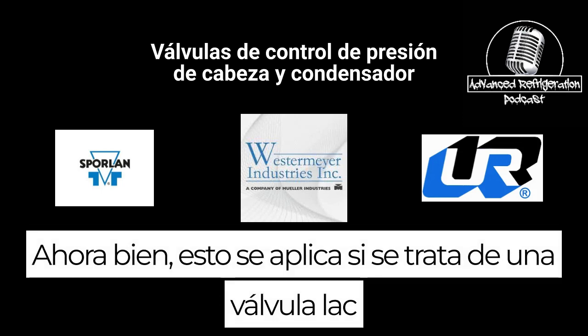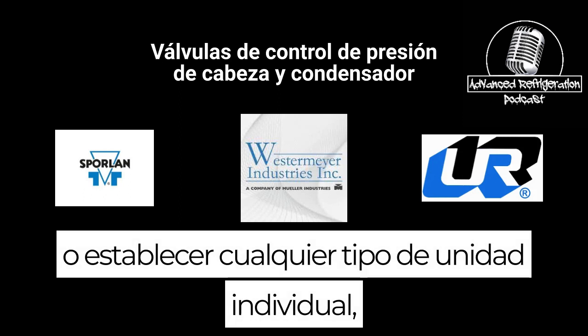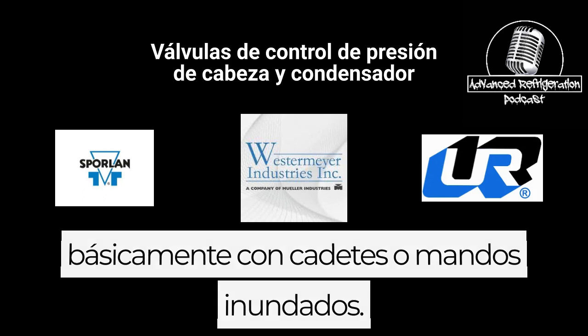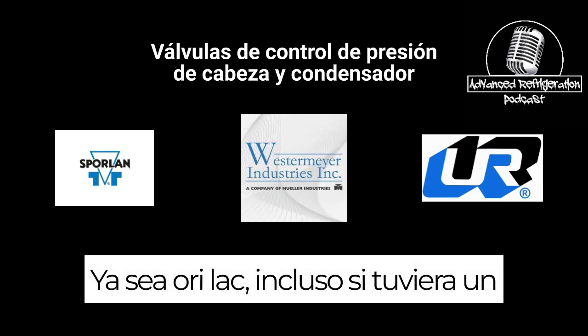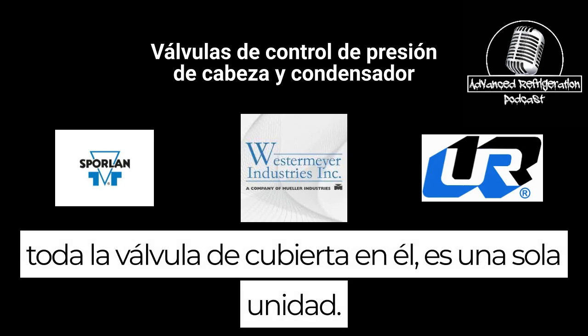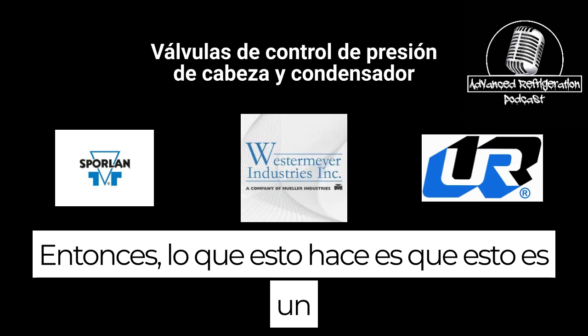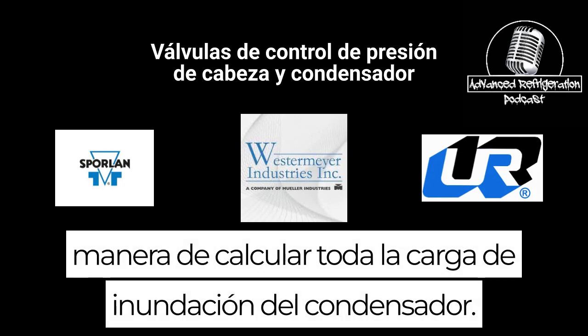Now, this applies whether it's an LAC valve, ORI, or an ORD, basically any kind of single unit set up with flooded condenser controls, whether it's ORI, LAC, like I said, even if it had a full back valve on it, it's a single unit. So this is a way to calculate your entire condenser flooding charge.